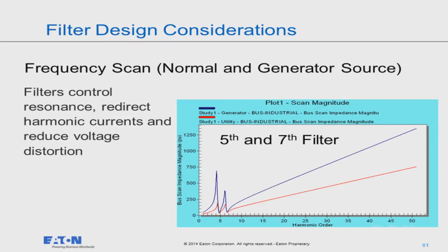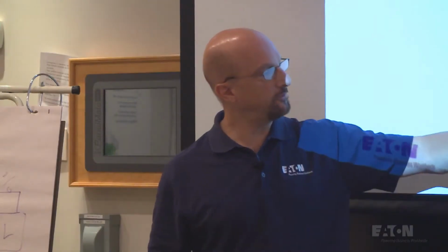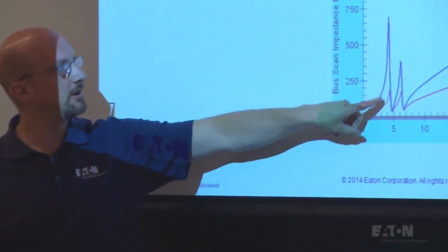What happens is, you notice this is impedance, and this is harmonic order. If you put just a fifth harmonic filter on, you get that curve. If you put just a seventh on, you get that, but then this would actually go up here. The impedance at the fifth harmonic now would be worse than it was before, and you would actually have a thing called a resonant condition. You would actually amplify the fifth harmonic.